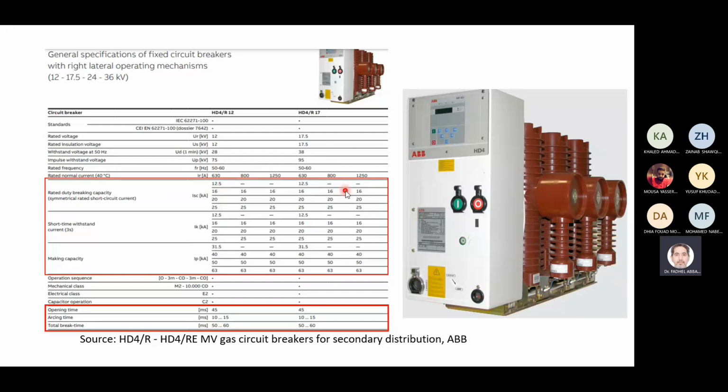أضيف لها 25% عشان آخذ كأنه الدي سي، لأن الدي سي أتوقع ما بيزيد عن 25% حق ديستريبيوشن بريكرز، مو حق نتكلم عن جنريتور بريكر. جنريتور بريكر الدي سي كومبوننت كان جو higher than 17، الإكس آر ريشيو 17.